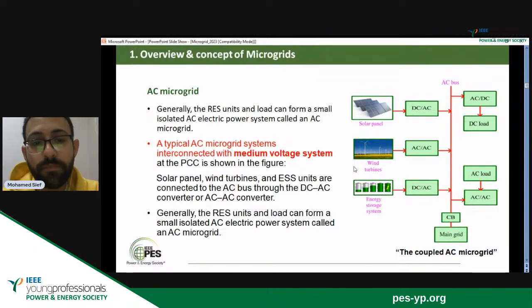A typical AC microgrid system is interconnected with medium voltage and contains these components. Medium voltage level is really important, for example for a factory. Most factories are connected to the medium voltage level of the grid, so it's more economical to install this microgrid and connect it directly to the main grid, avoiding long cables or additional transformers to step down to low voltage.